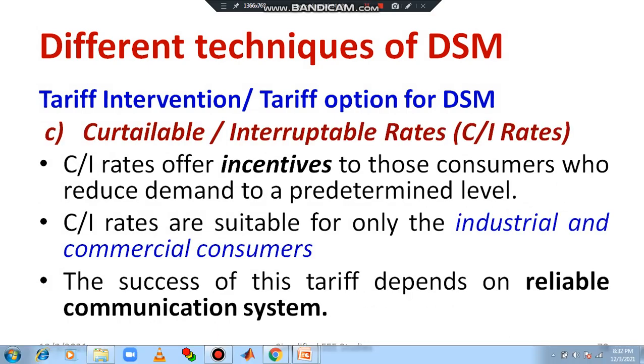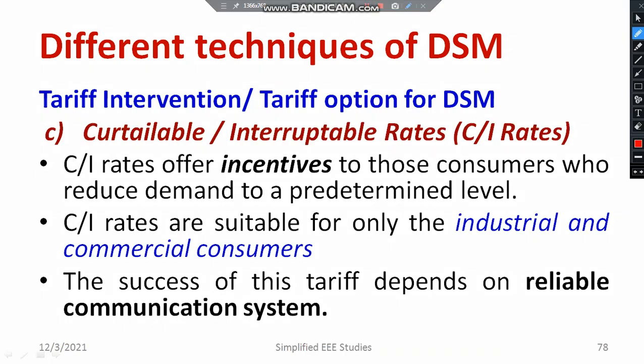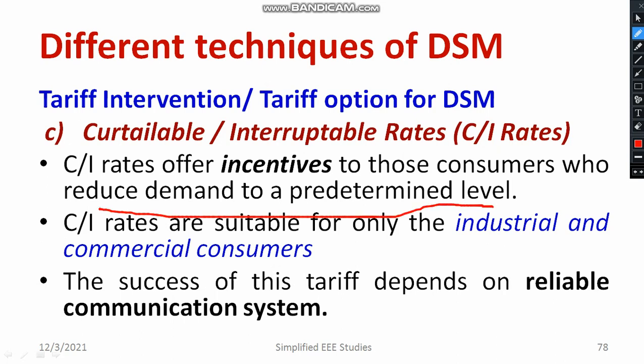Let us see what is curtailable or interruptible rate tariff. In this type of tariff, the main importance is given to customer demand. If a customer reduces their demand to a predetermined level, the cost of electricity comes down — that is known as curtailable or interruptible rate. There is a predetermined maximum demand in terms of kilowatts. If the customer reduces and comes down to that particular demand level, the cost per unit will also be reduced.